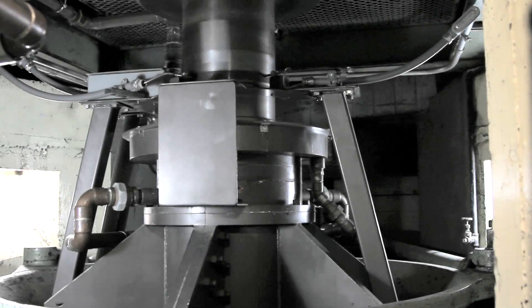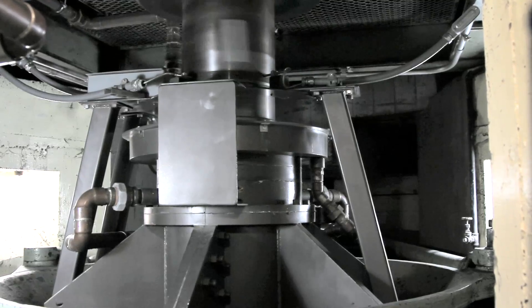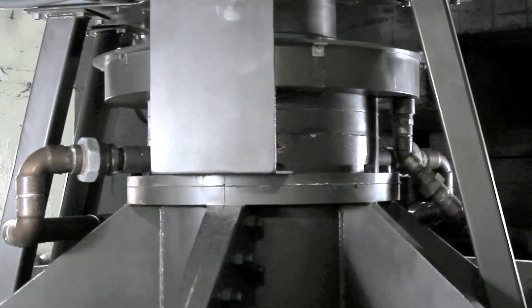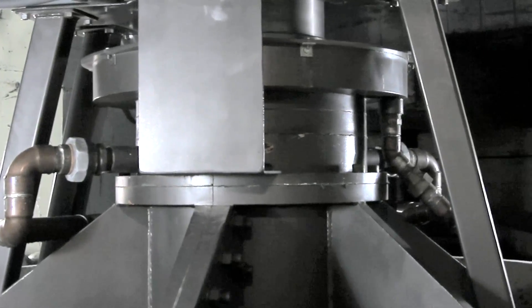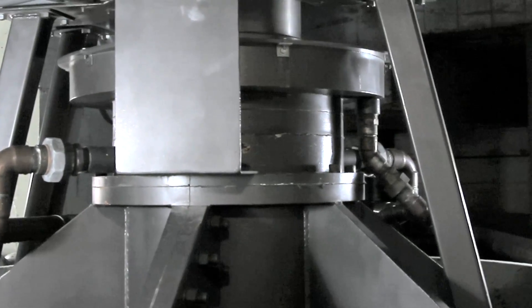In this view of a larger previously converted turbine, you can see the seal water basin on top, catching the water leaking past the seal and delivering it downward through the copper pipe on the left and into the integral discharge duct leading to the low pressure area above the runner. In other turbines, the bearing discharge may have to be piped away rather than using this convenient method of disposal.